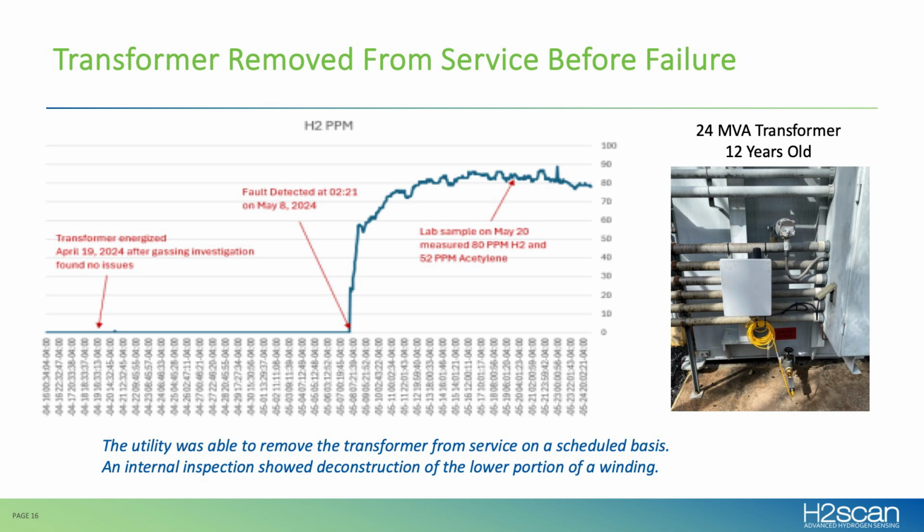If they would have left it in service, it would have failed in some period of time, likely in a shorter time frame rather than a longer time frame. If they had waited for the next annual oil sample, it's likely this transformer would have failed prior to the next sample. So again, 12-year-old transformer, and there's great technology out there today that allows you to monitor these transformers.